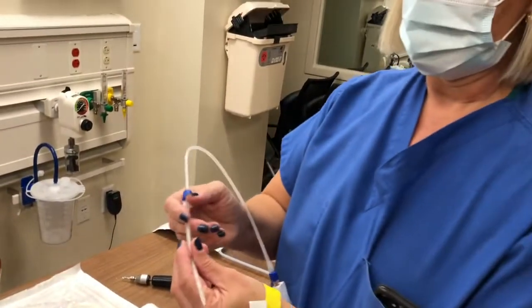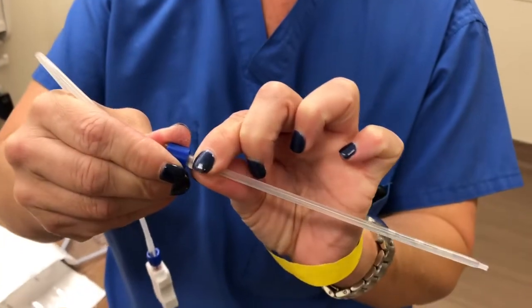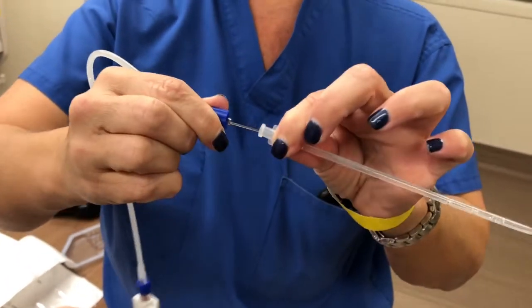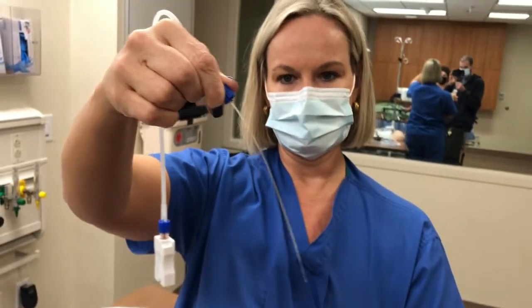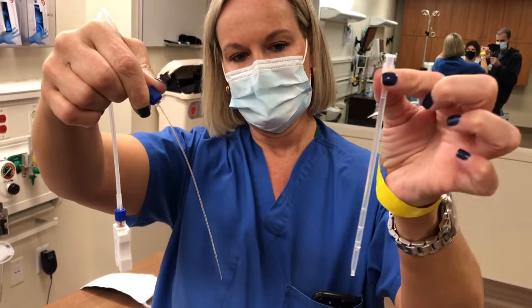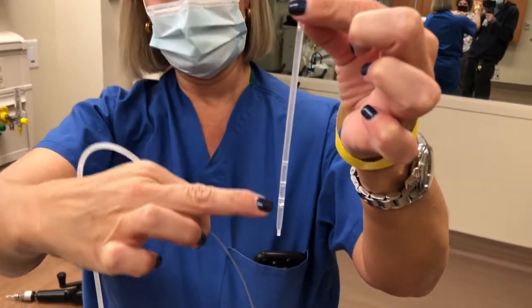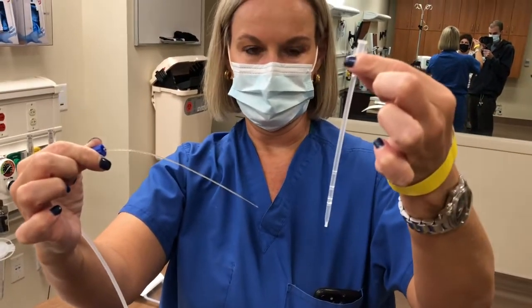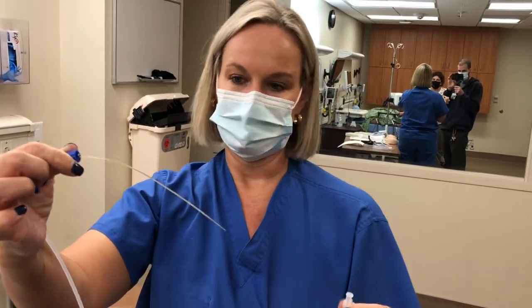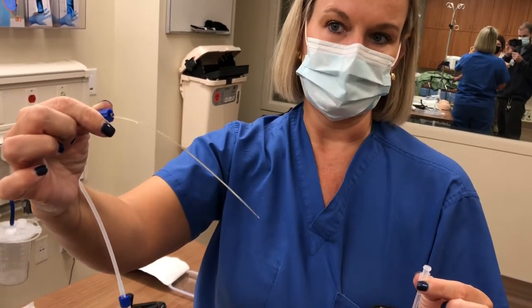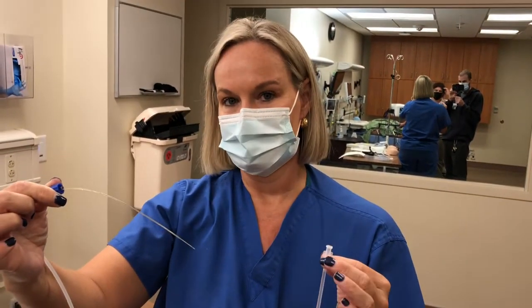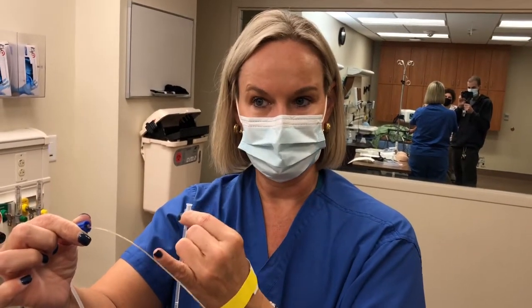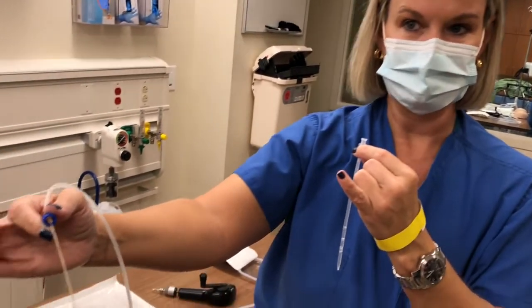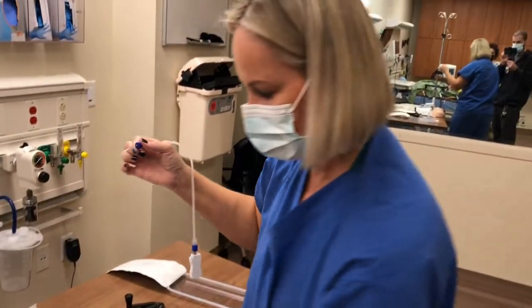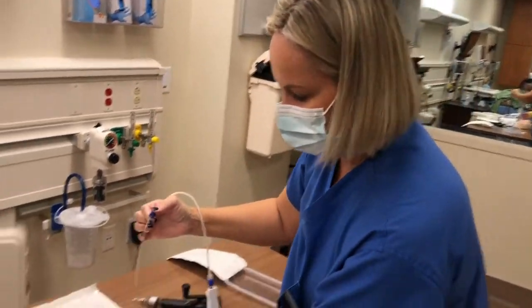So there is a covering here. When I take this off of the device probe, notice that this is moist. I don't know if you can see that or not. Hopefully it's illuminated enough on the camera, but you actually see the electrolyte fluid that it's seated and stored in. If this were to come out dry and you saw nothing at all, that it's not been in an electrolyte bath within its encasement, then you need to stop, go grab another one out of the refrigerator because this is not good. And remember, what you would be doing is that this right here is serial number 567, so that means that smart card needs to come out of the machine and a new one needs to be put in. But this one's nice and moist. It's been bathed in the electrolyte solution.